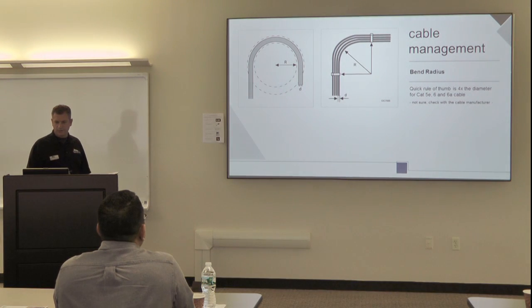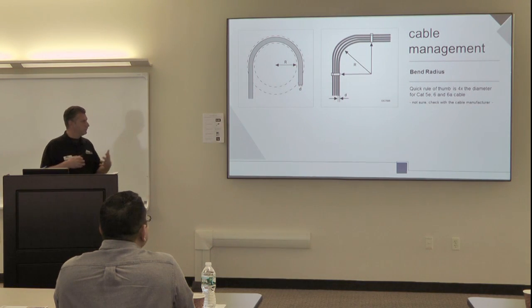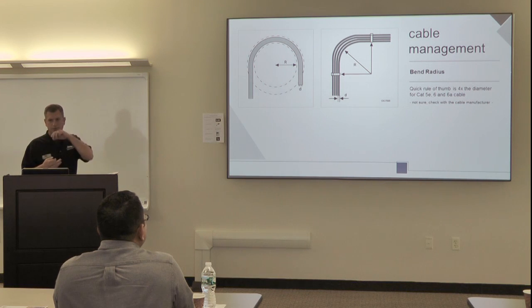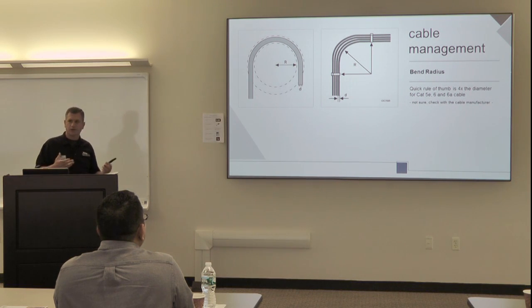For bend radius, check with the cable manufacturer when you can, but here's a rule of thumb. For category cables, if you don't have manufacturer specs, use 4 times the diameter of the cable—check the cable's diameter, and 4 times that gives you a good radius that won't cause issues.